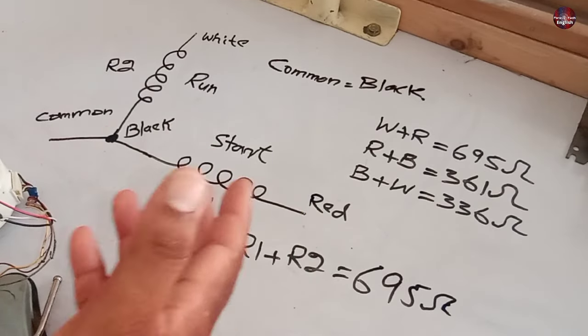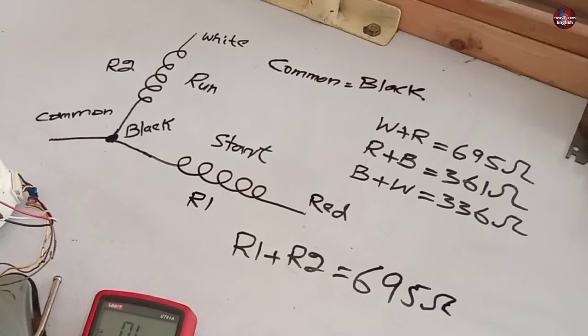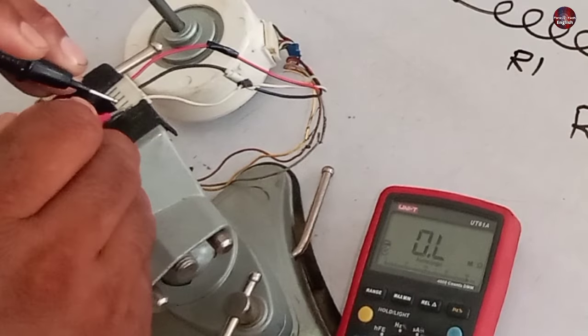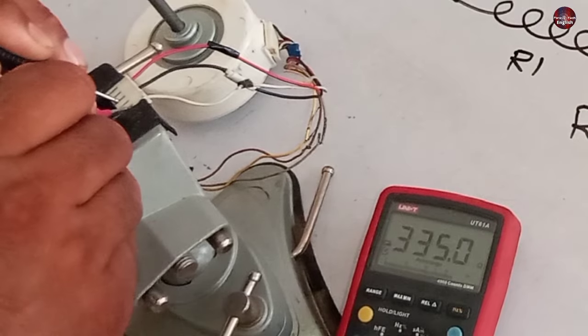Now we will find the running and the starting points. We already know what is the running and the starting point right now. But in case we don't know, then how will we find the running and start wires? For that, when I am checking the black and white wires, the multimeter is approximately showing 336 ohms.